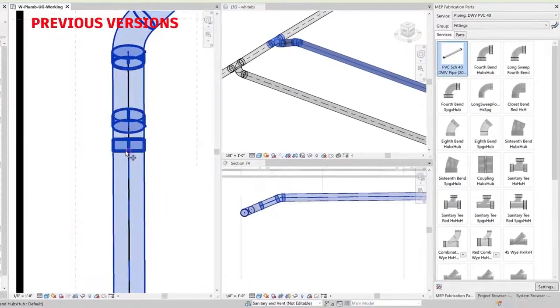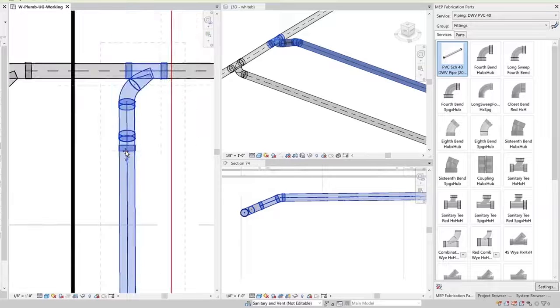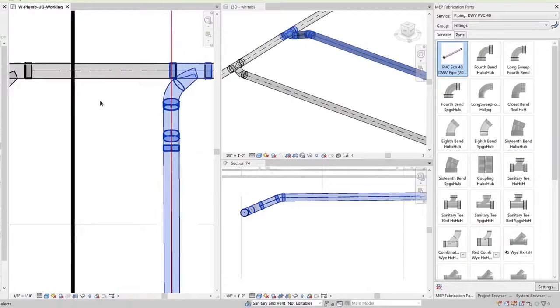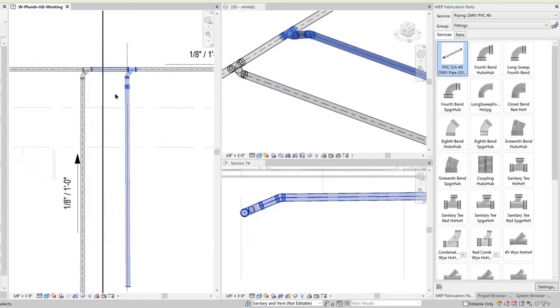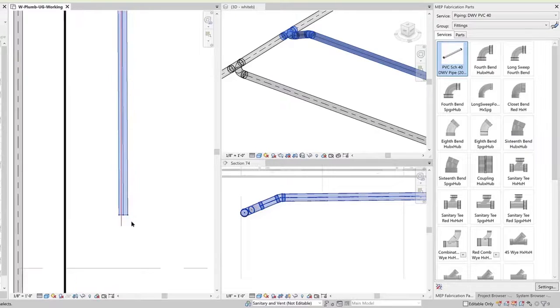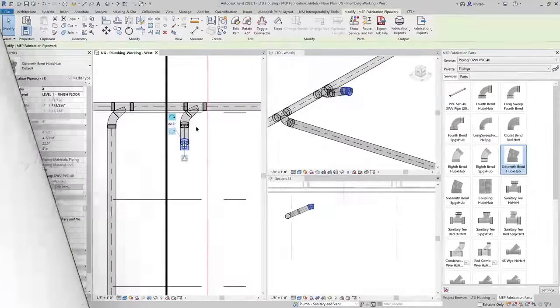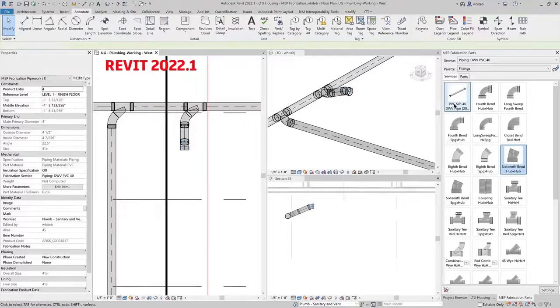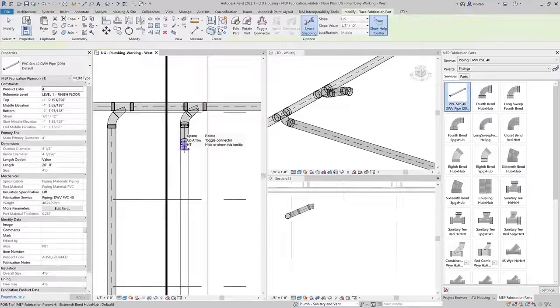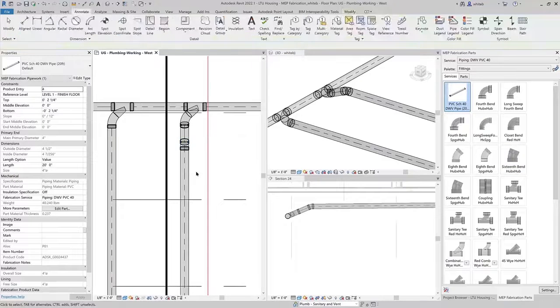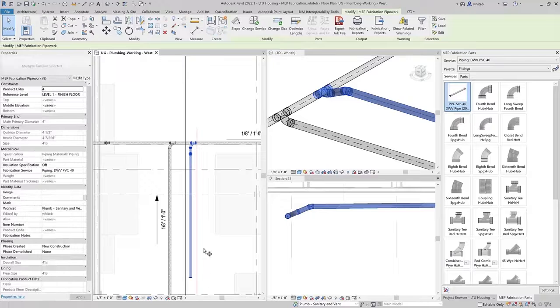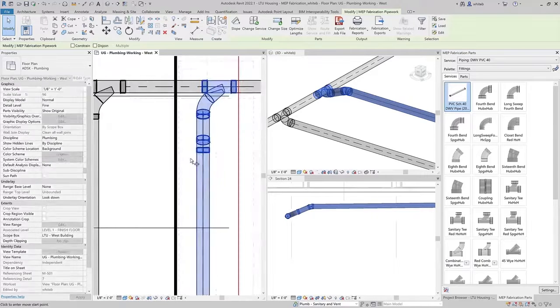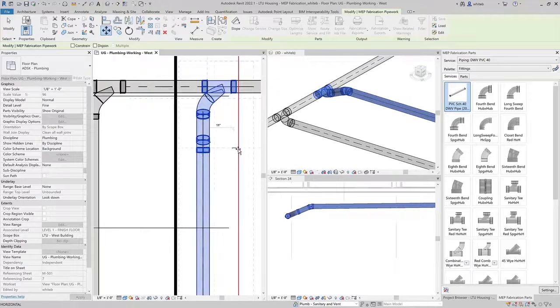In previous versions of Revit, rigid fittings did not allow main and branch work to maintain perpendicular alignment automatically when modeling a sloped layout. The user needed to take the extra step of manually aligning the branch in plan views. With this release, Y-fittings automatically adjust to maintain perpendicular alignment for sloped layouts using fabrication parts, saving you time and effort when detailing.